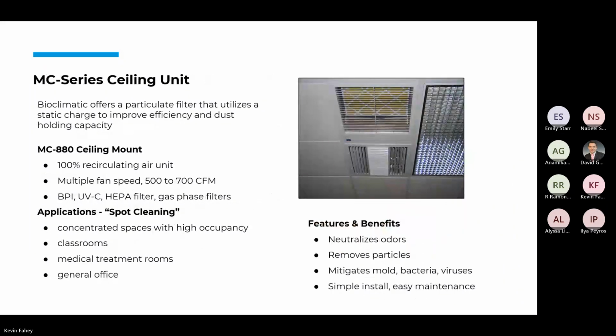So you get less pressure drop, less maintenance, and in the long run, total cost of ownership being less. And then there's also recirculating units, and these are popular for odorous environments as an auxiliary system to whatever other system is in, often used in pantry areas or food kitchen areas. These can be designed with a combination of technologies. They're recirculating, and they're going to have 500 to 700 CFMs of air, which is usually good for about a 1,000 square foot space. They fit in the size of 2 ceiling tiles, about 2 by 4 feet. You can have UVC in there, you can have HEPA filters, you can have bipolar ionization. Depending on what the contaminants are and what we're trying to remove, we can help you with what technology to put inside of the recirculating unit.